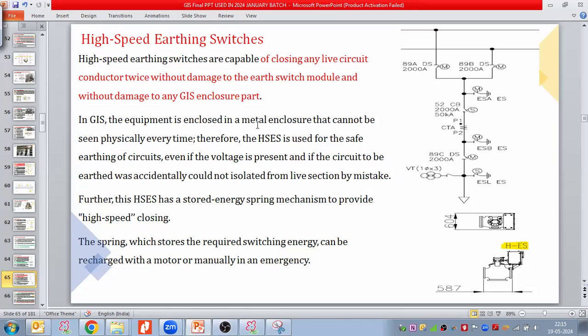In GIS, the equipment is enclosed. Now coming to why we take the high speed earthing switch. In the GIS, all the disconnectors, breaker, CT, VT, all equipment is enclosed in a metal enclosure that cannot be seen physically every time from outside. Therefore, the high-speed earthing switch is used for the safe earthing of circuits, even if the voltage is present, and if the circuit to be earthed could not be isolated from the live section by mistake. Further, this high-speed earthing switch has a stored energy spring mechanism to provide high-speed closing. The spring which stores the required switching energy can be recharged with the help of a motor or manually also in the case of emergency.